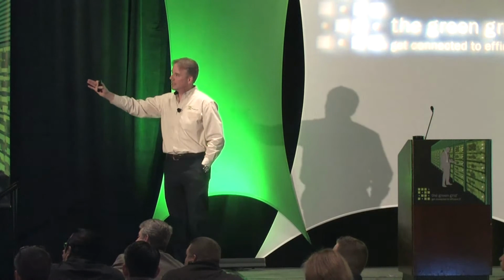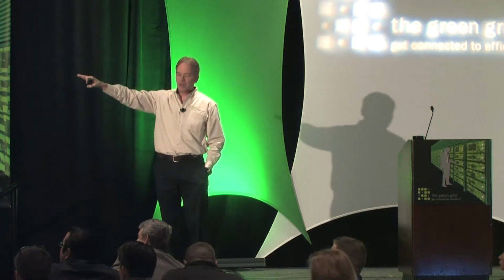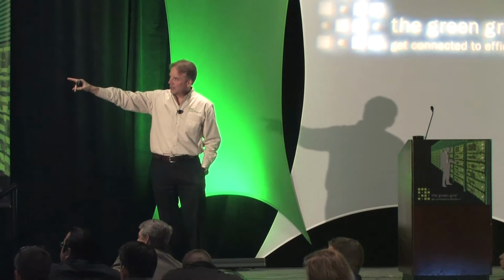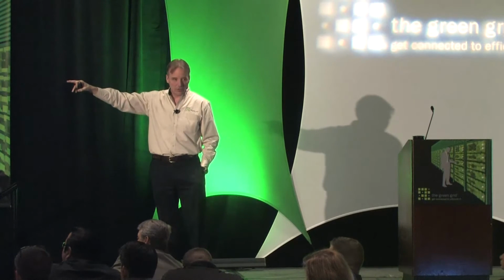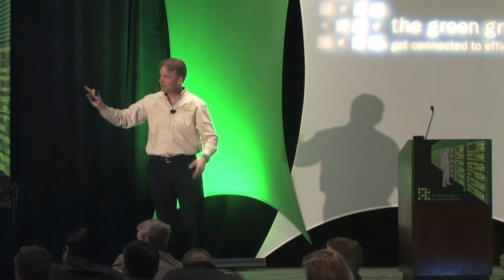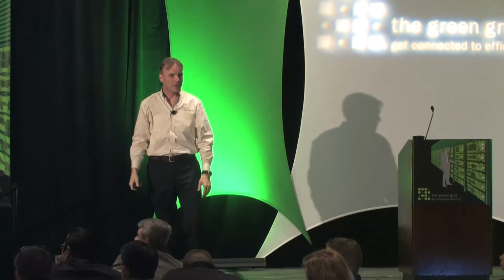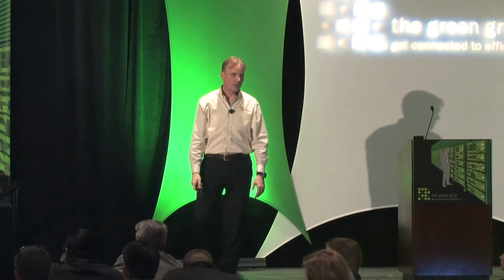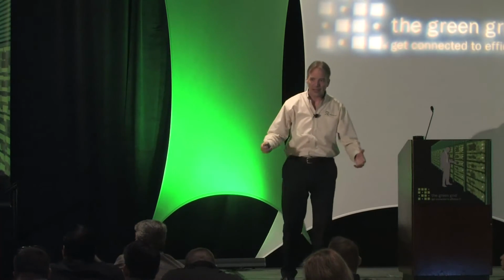But what I'm showing is, on the left side, the lunar lander, that's 2 modules. If you notice on the right, this is the second module added onto that. All those are servers, okay? We just haven't put the other pieces on yet around it. The one behind it is complete. That one, using adiabatic cooling, now will look like this one. But we're talking 550 kilowatts going into one of those containers, 1,920 servers in a 40-foot rack capacity space.